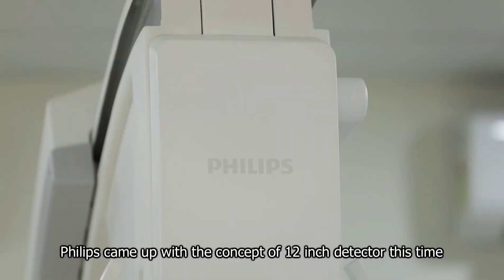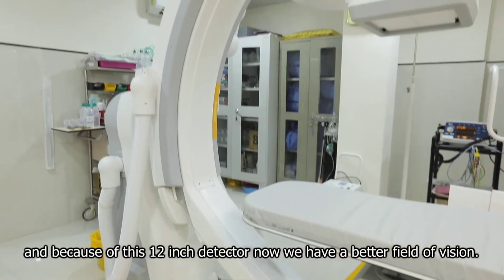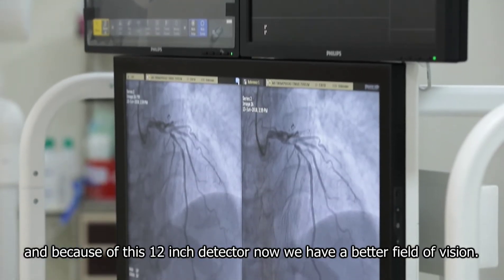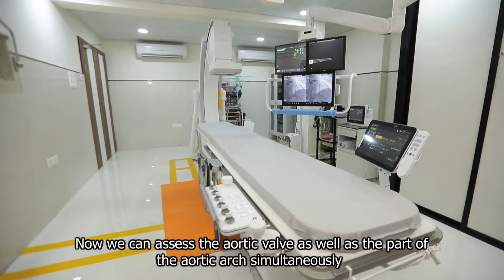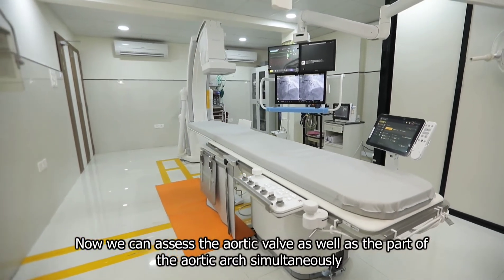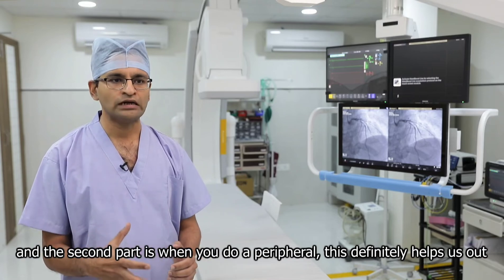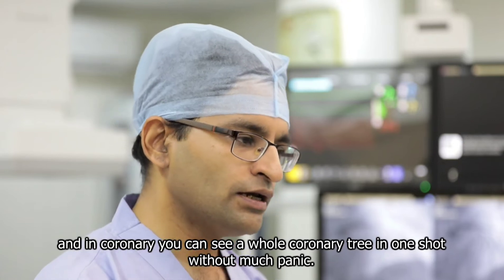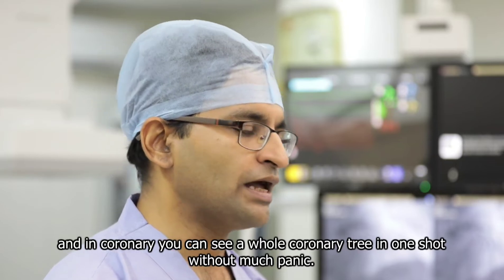Philips has come up with the concept of a 12-inch detector this time. Because of this 12-inch detector, we now have a better field of vision. We can assess the aortic valve as well as part of the aortic arch simultaneously. In peripheral cases, this definitely helps us. And in coronary cases, you can see the whole coronary tree in one shot without much difficulty.